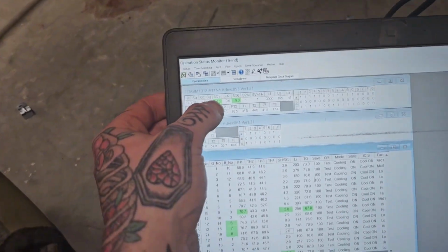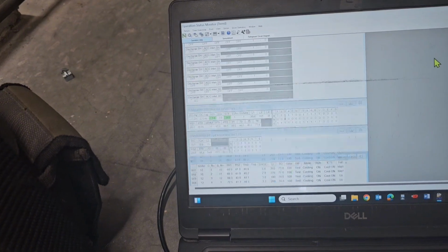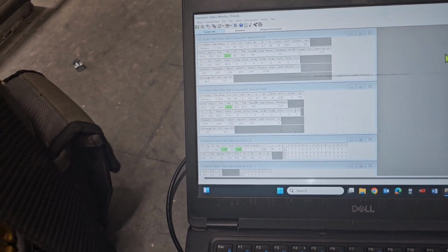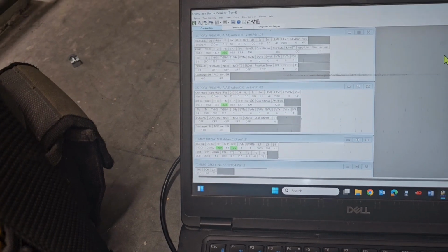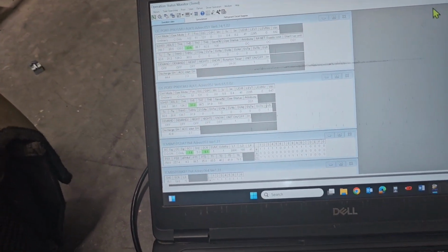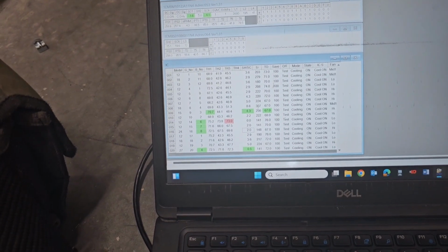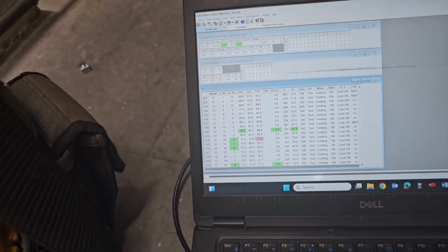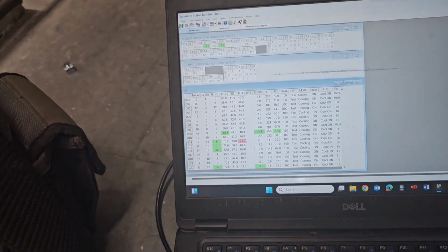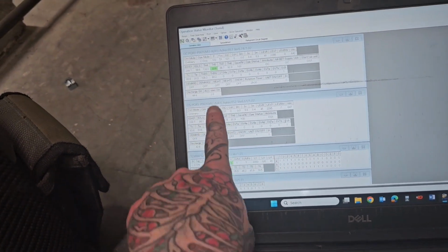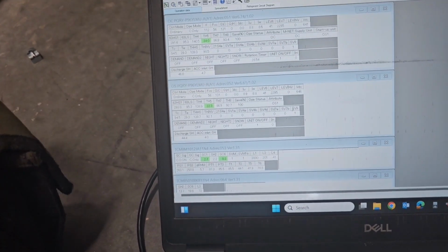Now we've got 2 degrees on SC1, 9 degrees on SC6, so that's slowly coming up. If we go back, I'll have to watch it for a little bit longer. It's probably because we don't have much superheat anymore, because again, there's not much load. We've got some units at 66, 68. So that superheat at our outdoor unit isn't as high as I would expect.